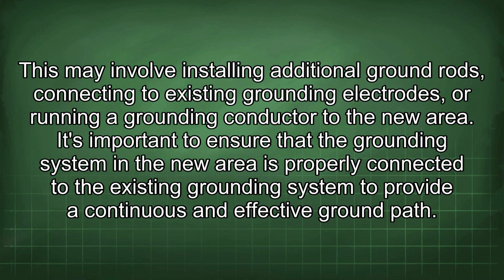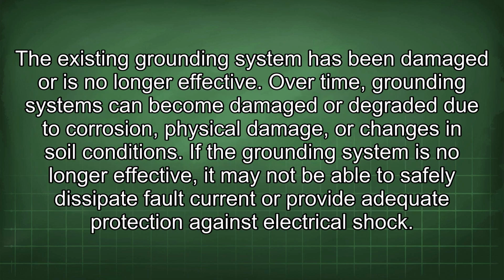This may involve installing additional ground rods connecting to existing grounding electrodes, or running a grounding conductor to the new area. It's important to ensure that the grounding system in the new area is properly connected to the existing grounding system to provide a continuous and effective ground path. The existing grounding system has been damaged or is no longer effective. Over time, grounding systems can become damaged or degraded due to corrosion, physical damage, or changes in soil conditions. If the grounding system is no longer effective, it may not be able to safely dissipate fault current or provide adequate protection against electrical shock.